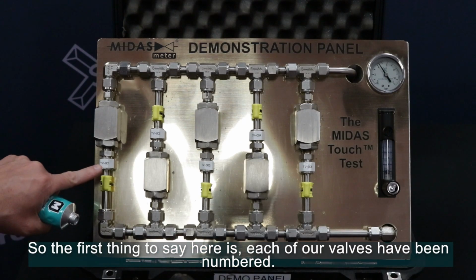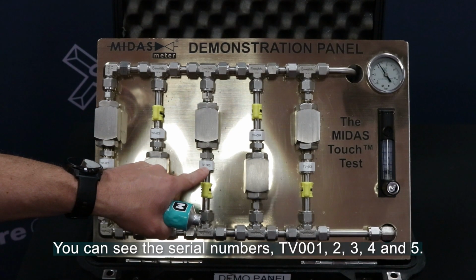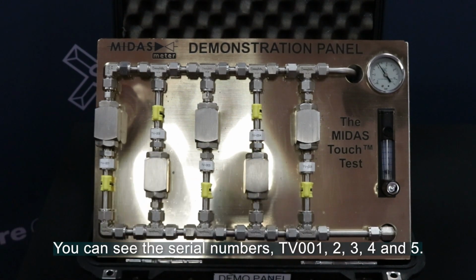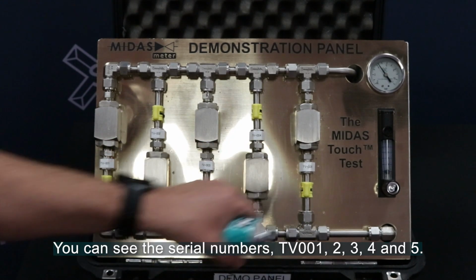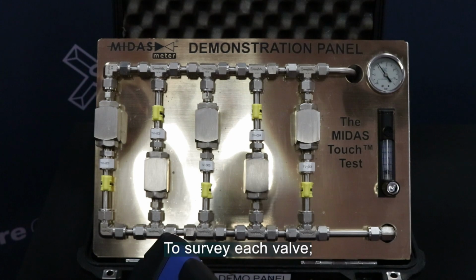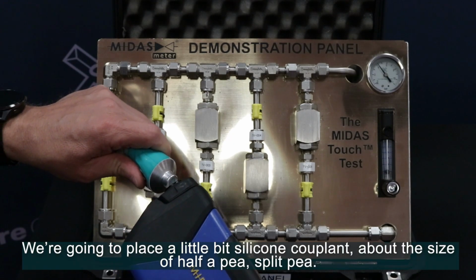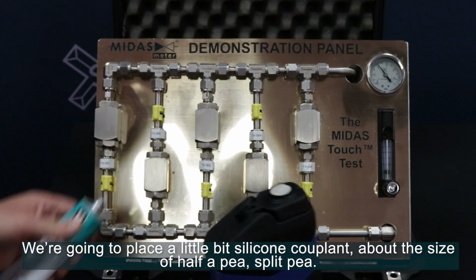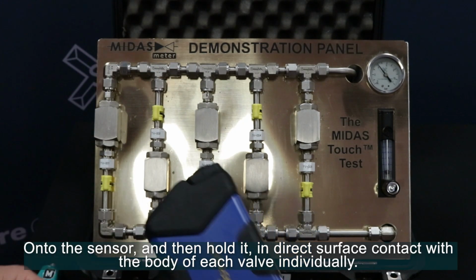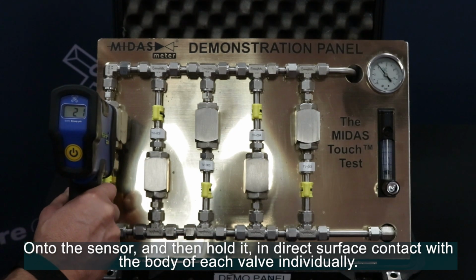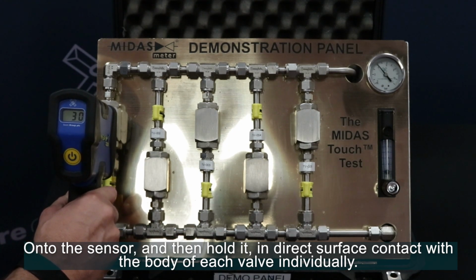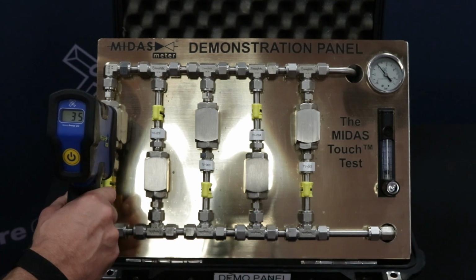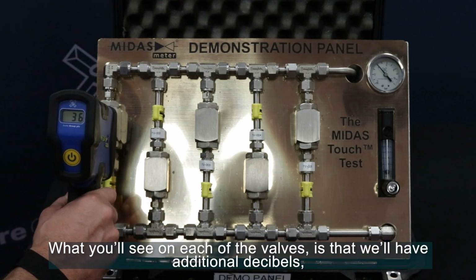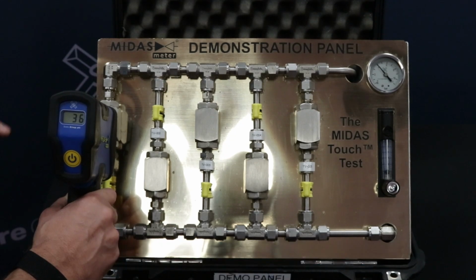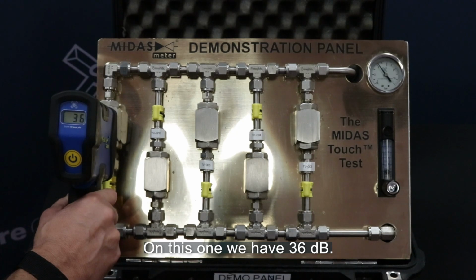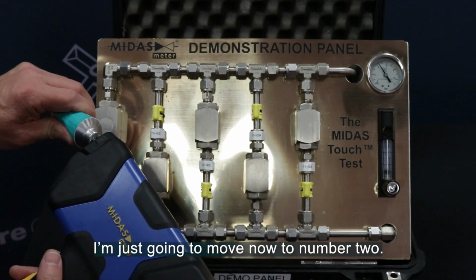So the first thing to say here is each of our valves have been numbered. You can see the serial numbers TV001, 2, 3, 4 and 5. To survey each valve, we're going to place a little bit of silicone couplant, about the size of half a pea, split pea, onto the sensor and then hold it in direct surface contact with the body of each valve individually. What you'll see on each of the valves is that we'll have additional decibels. In this one we have 36 decibels. I'm just going to move now to number 2.